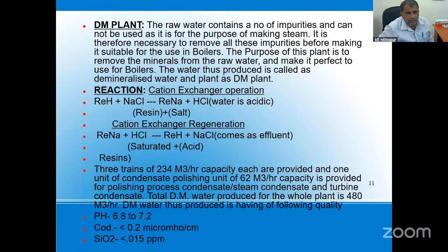Boiler tube damage is not good for the health of the boiler, because if you see the boiler, it is very compact in design. To identify tube leakage is not an easy task, and to replace the tube is also not easy, because very sophisticated technology is required for welding boiler tubes. So all industry avoids using raw water as boiler feed. Hence, the DM plant is mandatory to run a boiler.